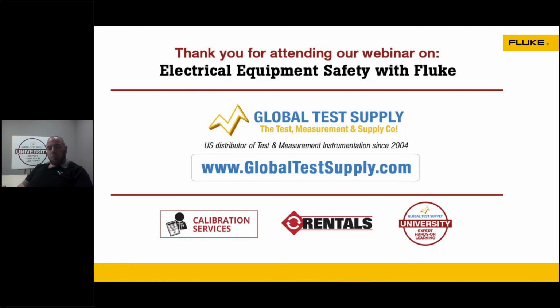Oh, that is a good question. So I would probably call that a category 3 because you're on a bus, you're on a VFD drive, it sounds like, right? Or a bus bar. Yeah, I would definitely call that a category 3 environment. Any voltages that are that high, I would push it to the higher level. No matter what, think about it on that safety level. A higher category rating is going to give you more safety. If you're working in this environment, I would obviously push to a category 3 1000 volt, category 4 600 volt type of meter. That category 3 1000 is going to put you in the right area.